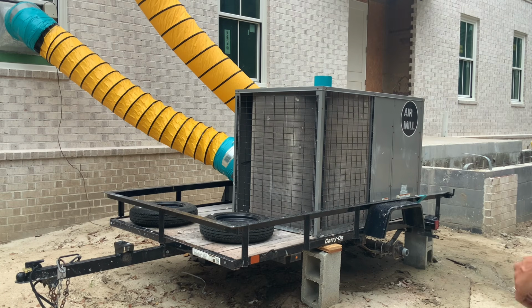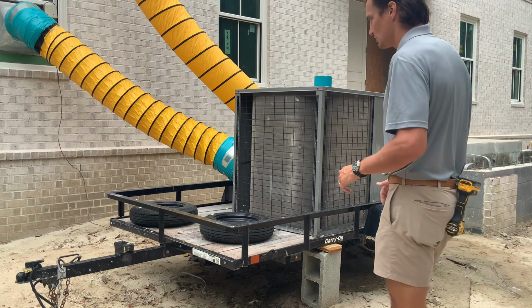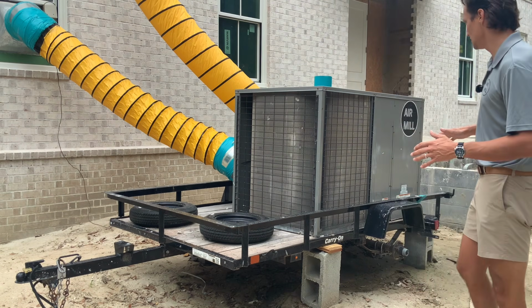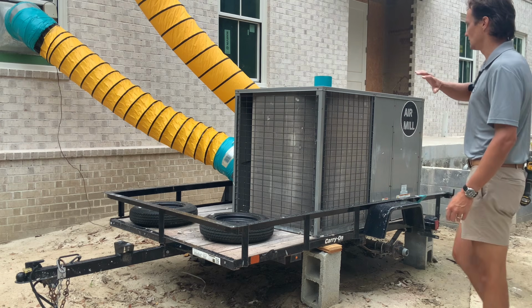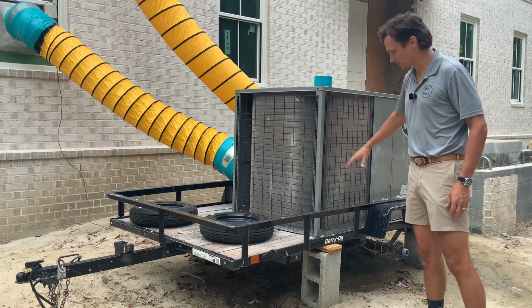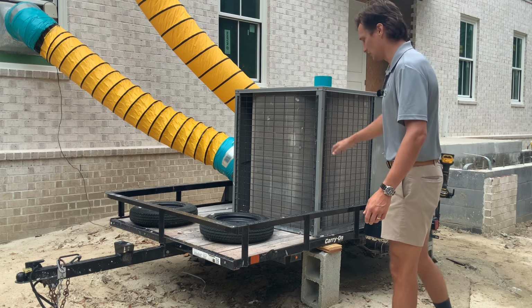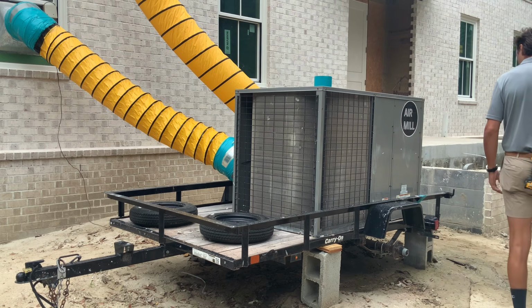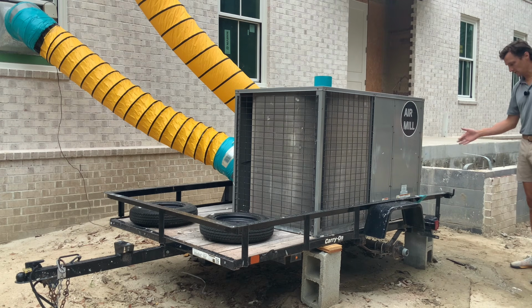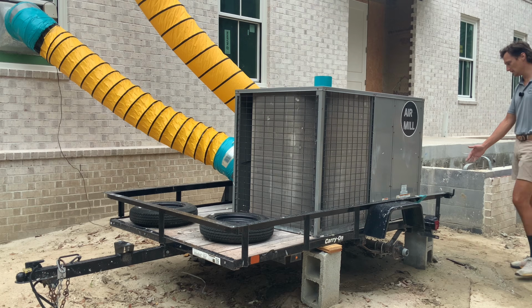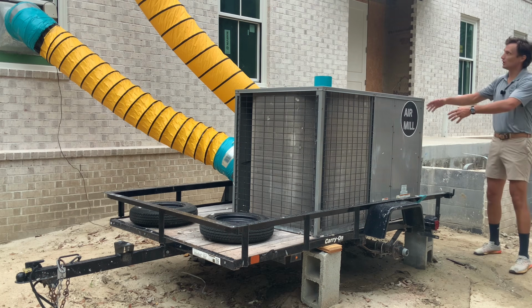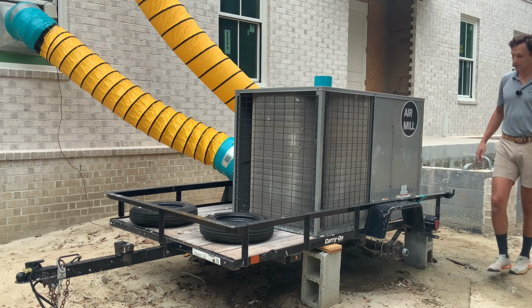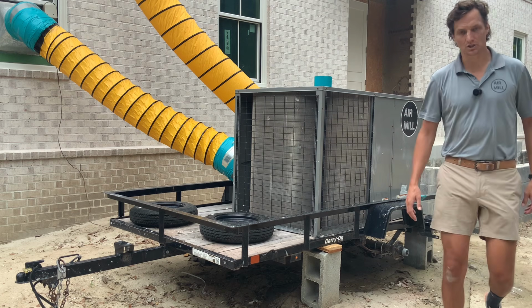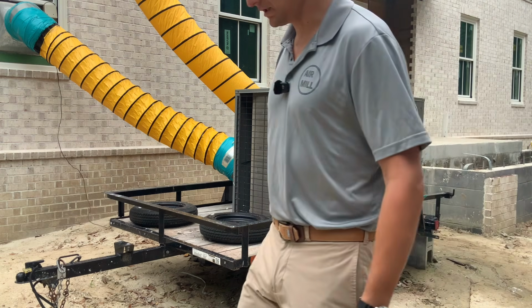The final part of the filter change process is checking on the machine, making sure that it is relatively clean, that it's not super dirty on the outside, that there's not a lot of trash or debris on the trailer. Make sure that the machine is dripping, leaking out condensation out of the condensation drain as it should be. Make sure that all the ductwork looks clean and organized, is not damaged, and there's no kinks in the ductwork.